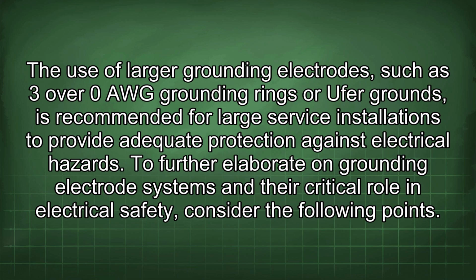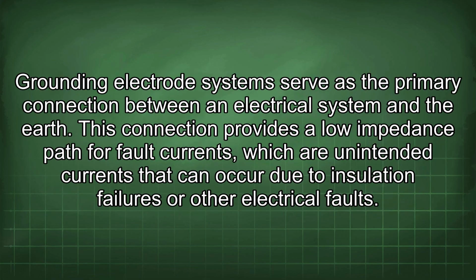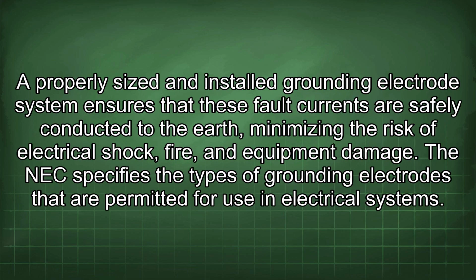To further elaborate on grounding electrode systems and their critical role in electrical safety, consider the following points. Grounding electrode systems serve as the primary connection between an electrical system and the earth. This connection provides a low impedance path for fault currents, which are unintended currents that can occur due to insulation failures or other electrical faults. A properly sized and installed grounding electrode system ensures that these fault currents are safely conducted to the earth, minimizing the risk of electrical shock, fire, and equipment damage.